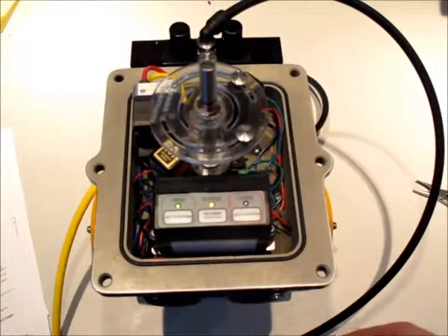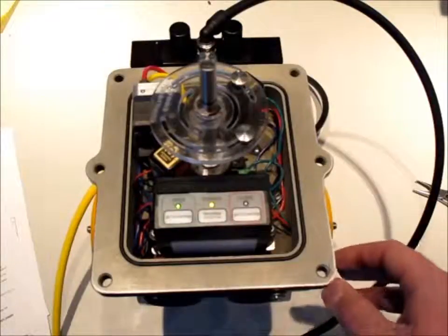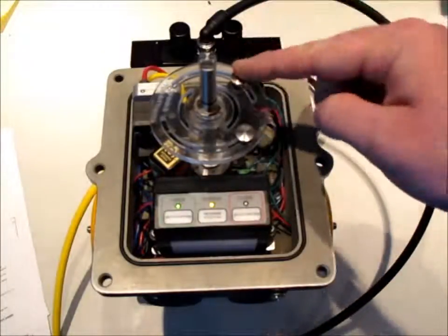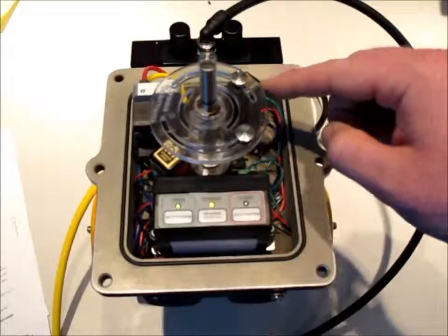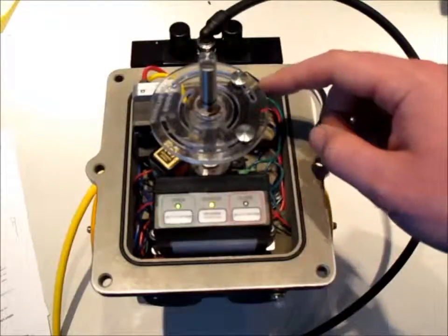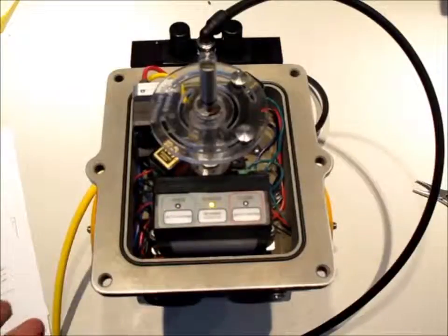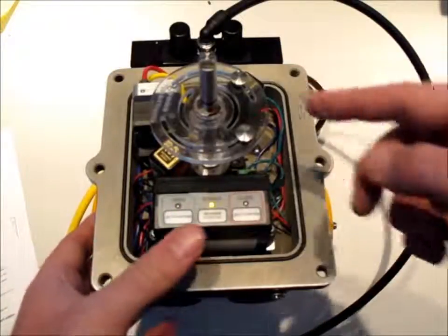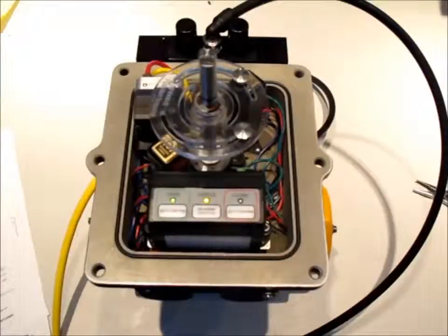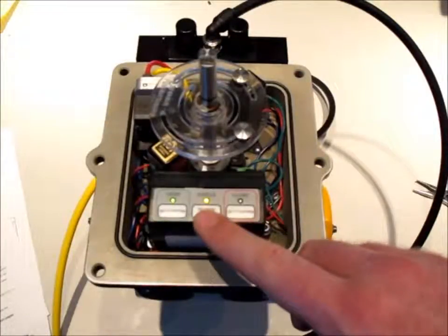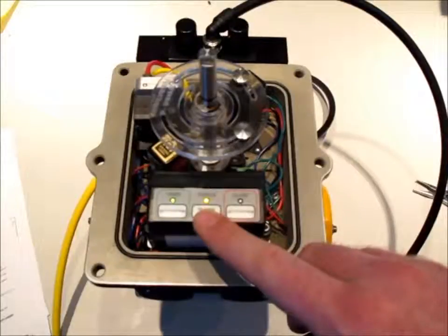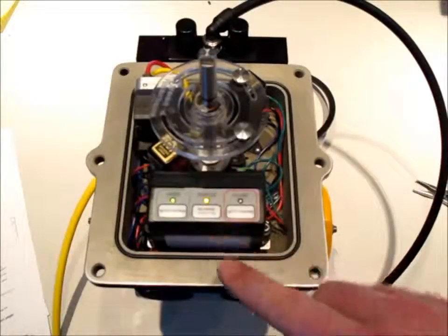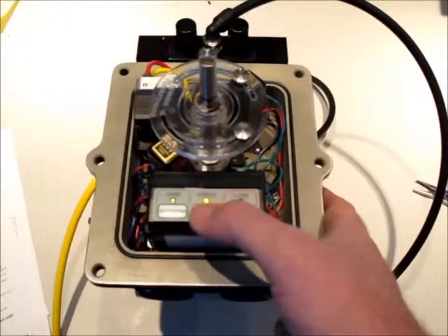Once you've moved to the open side of the actuator, confirm that your open magnet is over top of the open switch. Once again, hit set to blinking, the magnet's in place, and now confirm. You'll notice that the status light has changed from a flash to now a solid light. This is letting us know that it is indeed calibrated.